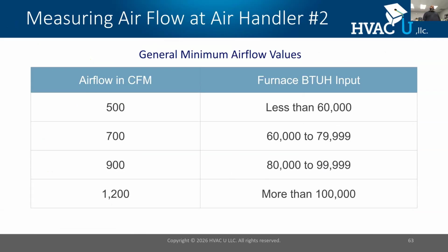Now, when we look at the air handler flow, they're generally designed to deliver flow based on their sizes. So if we look at a furnace input, if I have a 100,000 BTU furnace, many manufacturers, if you were to look up several of them, they all kind of land about the 1200 CFM mark. So we know that if we're in heating mode and we have a significant lower level of airflow, that's going to populate red when we start to make these kind of reports.